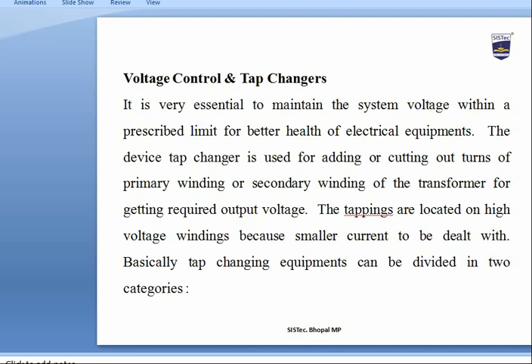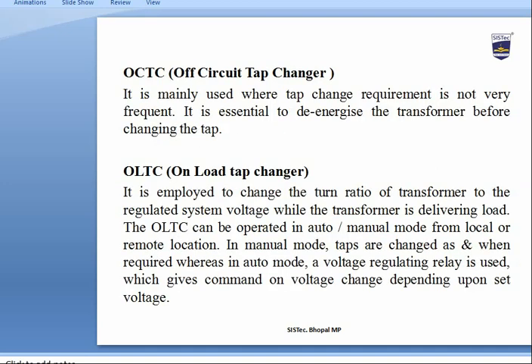Voltage control using tap changers is essential to maintain system voltage within prescribed limits. The tap changer adds or cuts out turns of the primary or secondary winding to get the required output voltage. Tappings are located on the high voltage winding — where smaller current is to be dealt with. Tap changing equipment is divided into two categories: OCTC (Off Circuit Tap Changer) and OLTC (On Load Tap Changer).